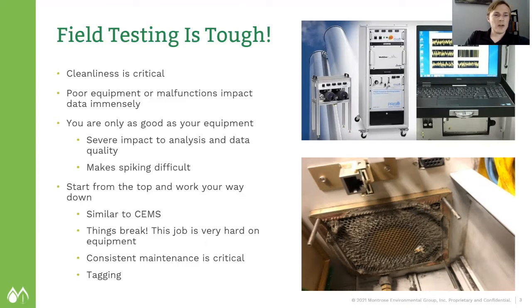Once again, I don't fault any of the test teams that do this line of work. It's notoriously difficult. But when you're going to be running an advanced instrument like the FTIR or the upgraded FTIRs, you need to make sure that your sampling systems are in really good working order. We tend to recommend dedicated sampling systems for each instrument. I know that's not always ideal, but if I was the customer, I would be making really sure that the equipment was clean and in good working order, because no matter how good of a spectroscopist, FTIR operator, whatever you want to call the person running the FTIR is, you're only as good as your equipment.